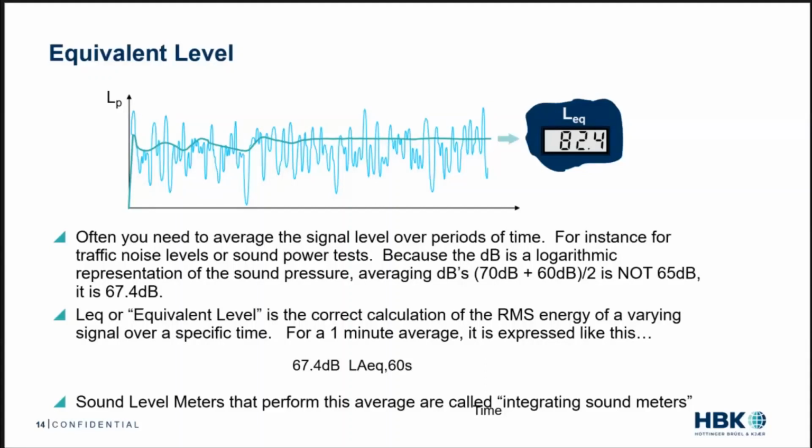The LEQ is the go-to measurement for most assessments of sound level. For product noise or environmental noise, LEQ gives you that physical quantity of sound exposure. The LEQ of the measurement is usually expressed as LEQ over the measurement period of time in reports. And again, we'll report it as A-weighted, with the A-weighted value on the report. Sound level meters that perform this average are called integrating sound level meters.